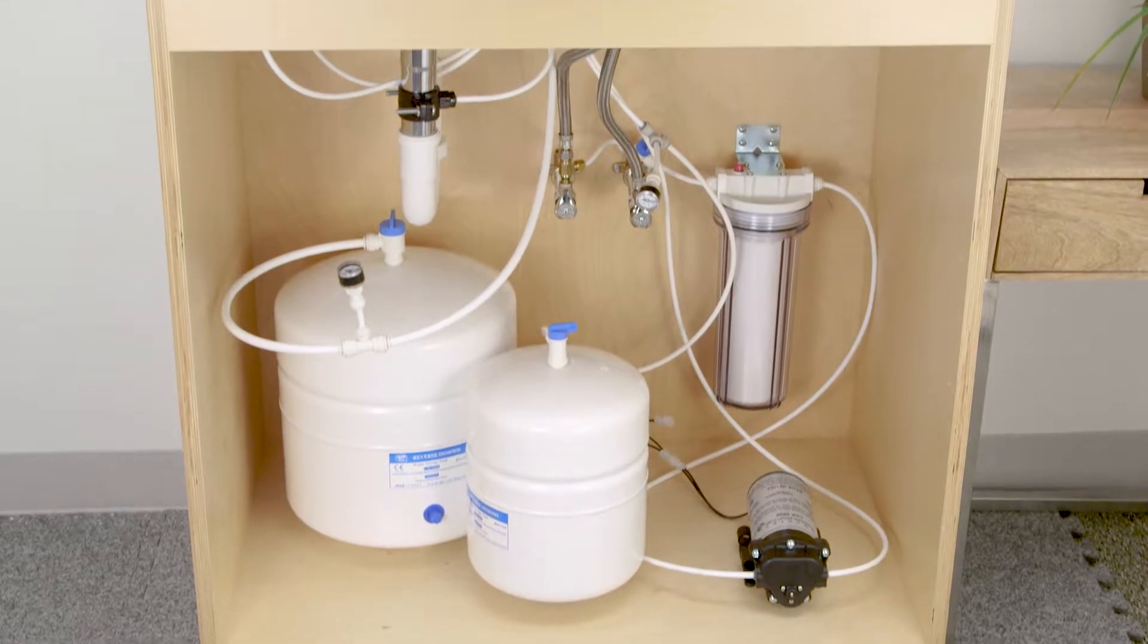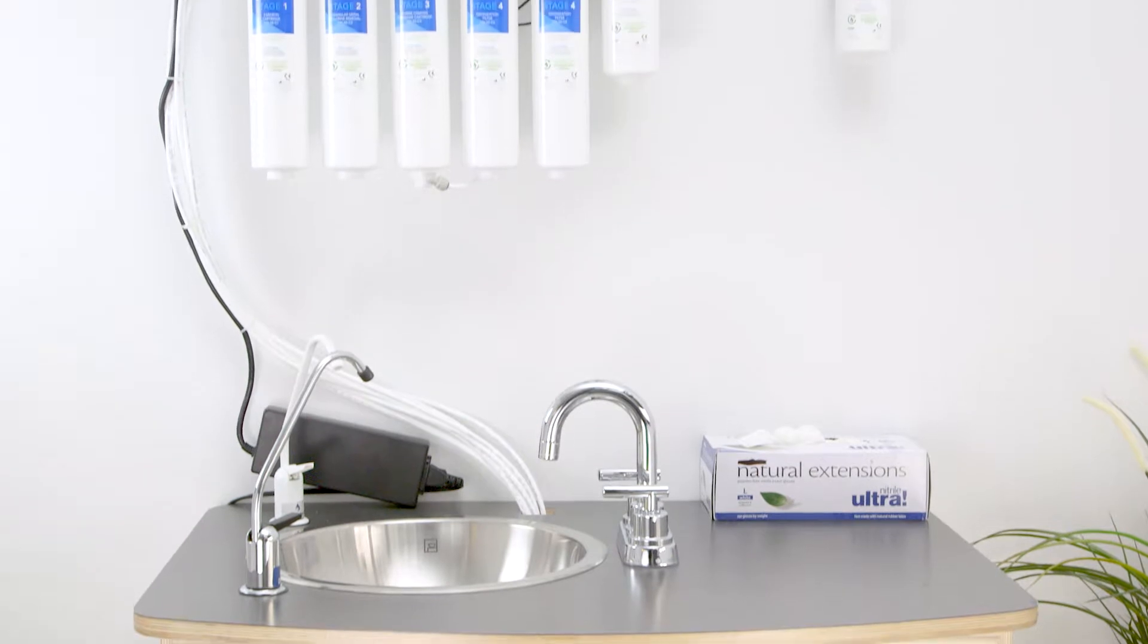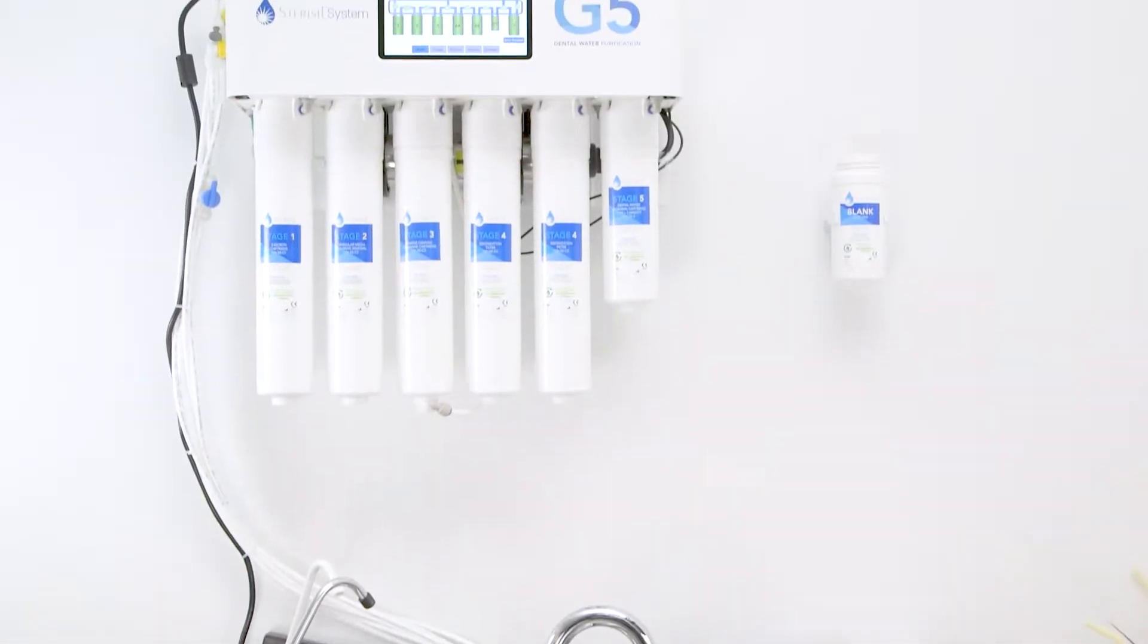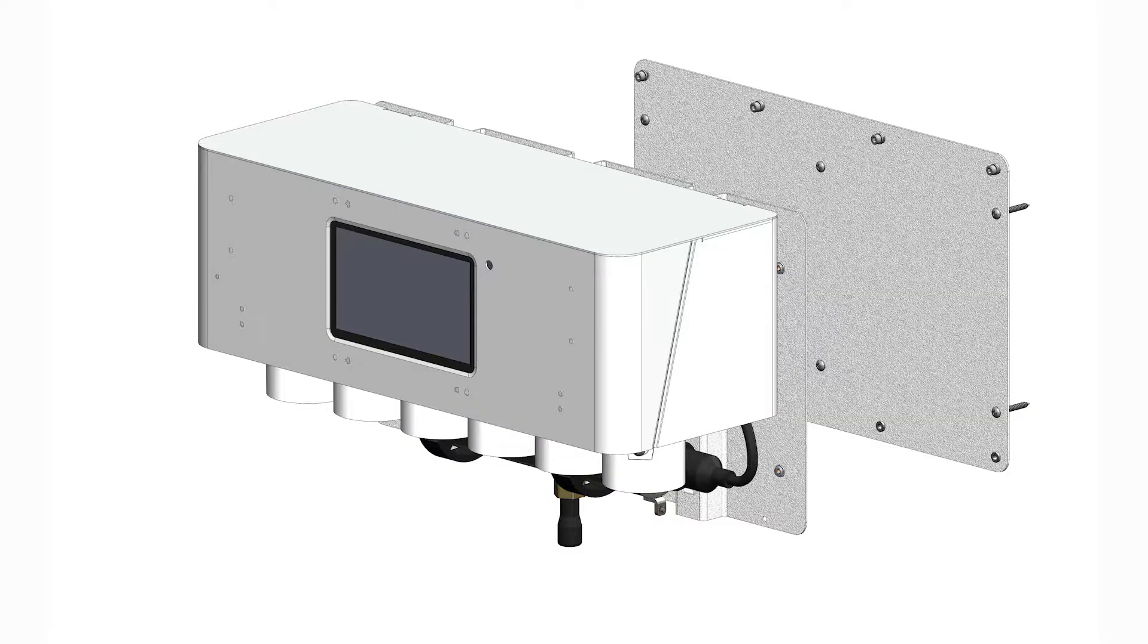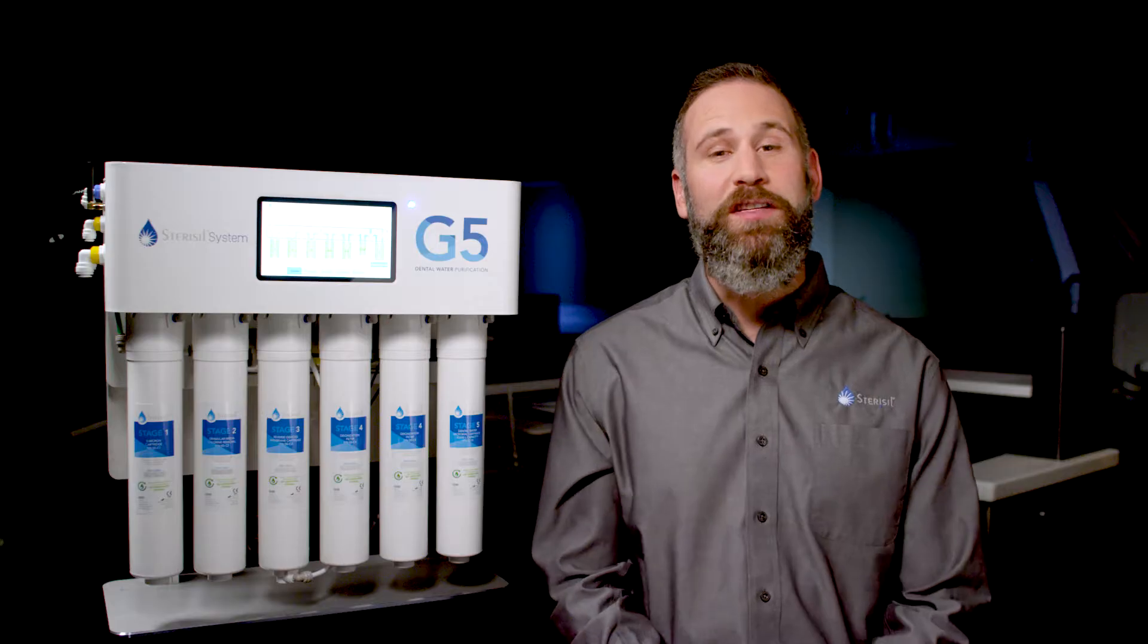The G5 can be mounted in one of three ways: an articulating arm wall mount, a sliding mount inside a cabinet, or a static wall mount. In this demonstration, we'll use the static wall mount method. The system weighs approximately 50 pounds when filled with water. For this reason, confirm the location of studs for proper anchoring.